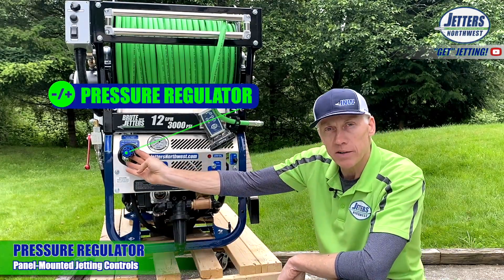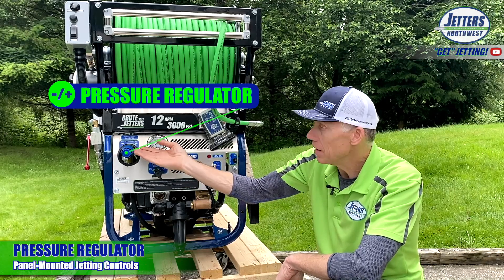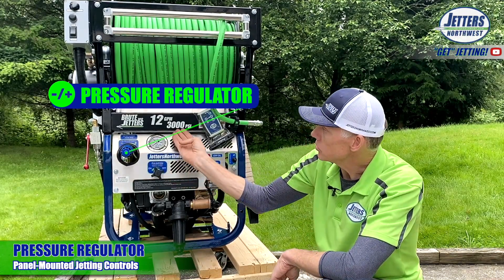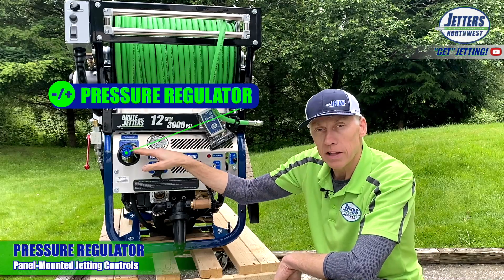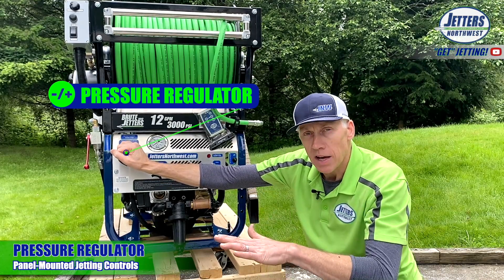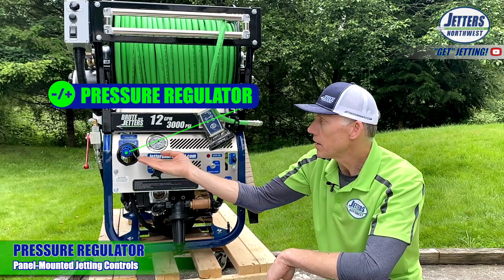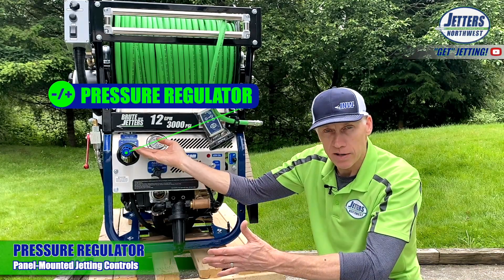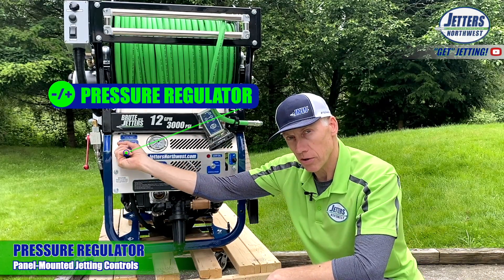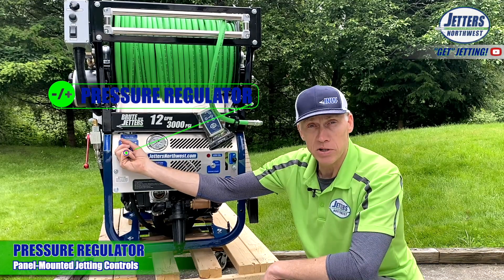Moving over, this is your pressure regulator — a pressure regulating unloader valve. What this does is if the pressure gets up above whatever this is set for. Out of the factory, it's going to be typically set for maximum. This machine is 3,000 PSI maximum, so the regulator is set for that. If you wanted to run at, say, 2,000 PSI max — for example, cleaning an Orangeburg or a soft pipe — you could back it off. No matter what you throttle up to, if pressure comes up to that set point, it's going to divert water back to the water tank. So if you want to adjust pressure, don't do it with the flow control valve — that is for jetting on and off. This is where you fine-tune your pressure with the pressure regulating unloader valve.